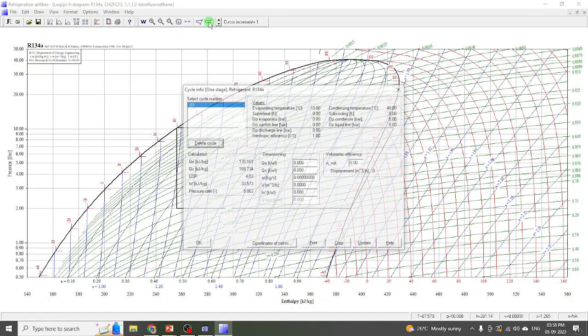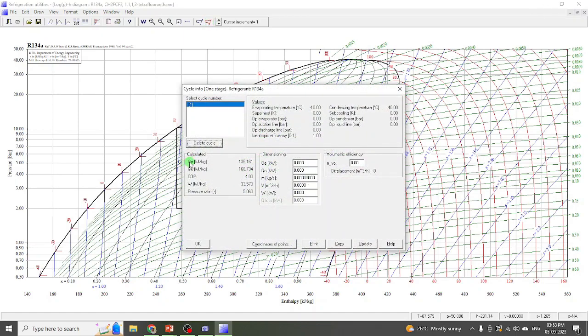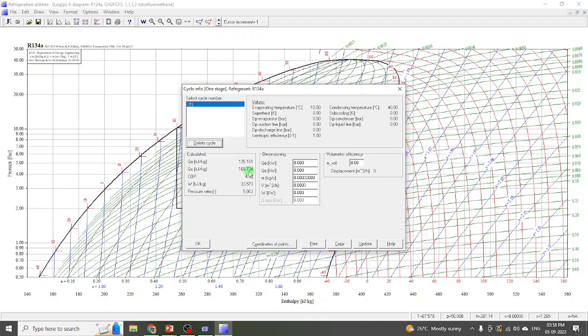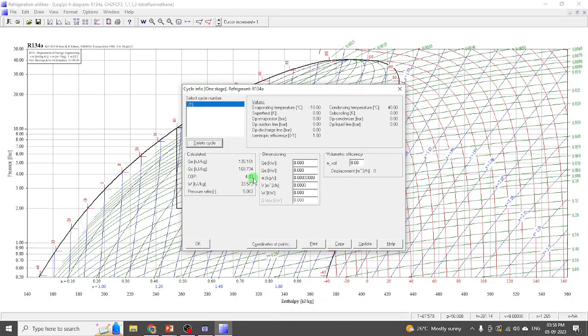Now we want the COP, how much heat is absorbed, how much heat is rejected — all those values you will get by clicking on the Show Info icon. You'll get values like how much heat is absorbed in the evaporator (indicated by Q suffix e in kJ/kg), how much heat is rejected from the condenser (168.734 in this case), and the COP value.